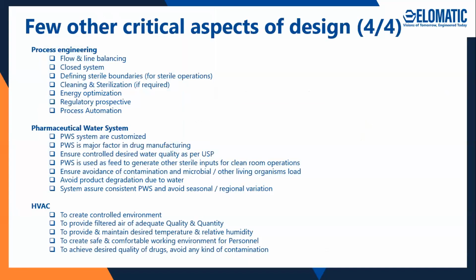The design engineer needs to know the process flow absolutely correctly to define and design the proper facility with the unit operations within it - whether it is an open system or closed system, whether it is single use or multiple use, depending on which system is chosen. Also, defining sterile boundaries specifically for sterile operations - the closer the sterile boundary is to the receiving vessel, the better it is.